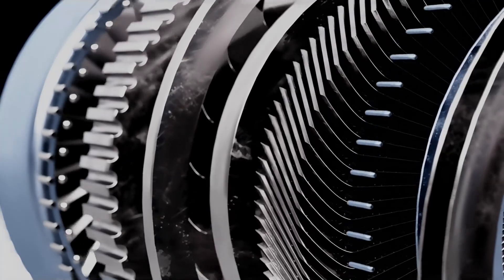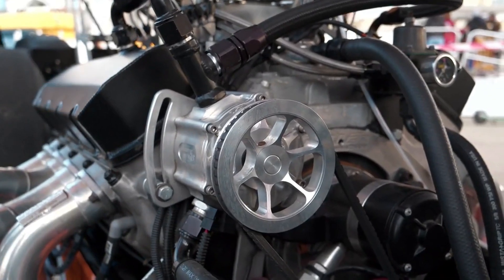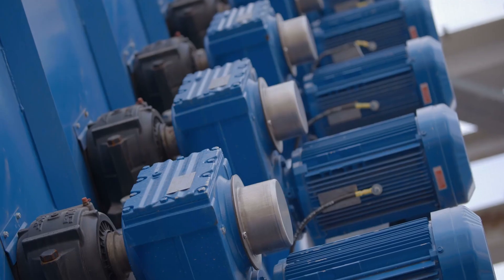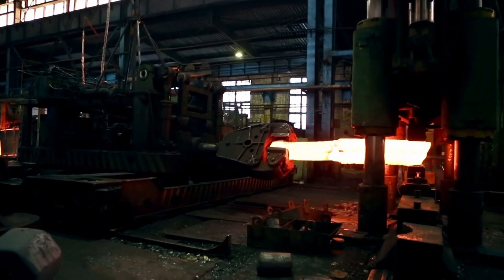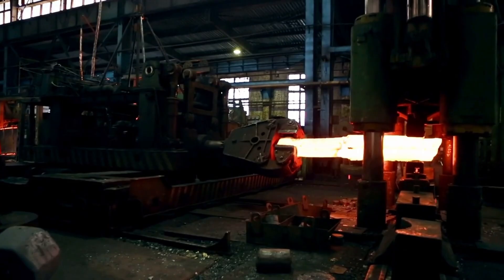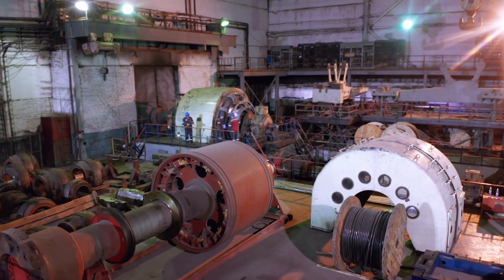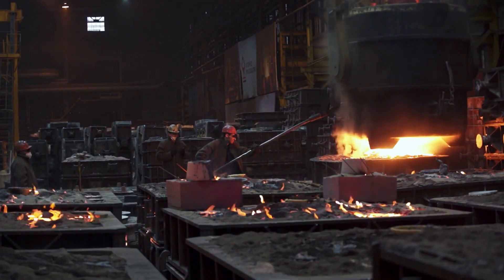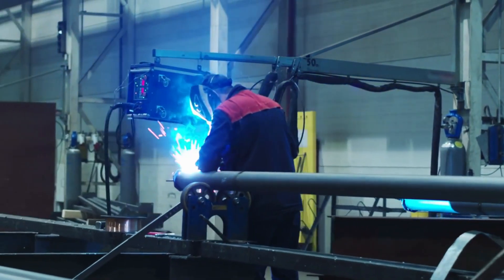That's a substantial leap from ABB's own previous world record of 99.05% set back in 2017. Efficiency ratings measure the ratio between the energy a motor draws and the amount it turns into motion. The theoretical limit is 100%, but every decimal closer to that limit is exponentially harder to achieve. That's why the previous record stood untouched for eight years, until 2025. This powerful motor in India will operate an air separation unit — liquefying the air around us to separate pure oxygen and nitrogen, gases crucial for steelmaking. Such investment in energy efficiency promises a remarkable return, with a payback period expected to be slightly more than three months.